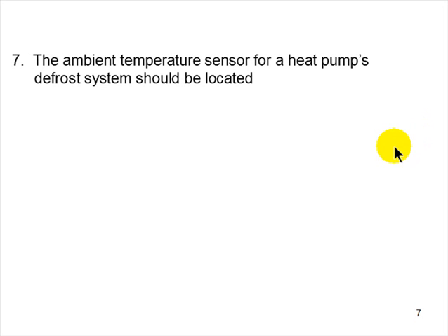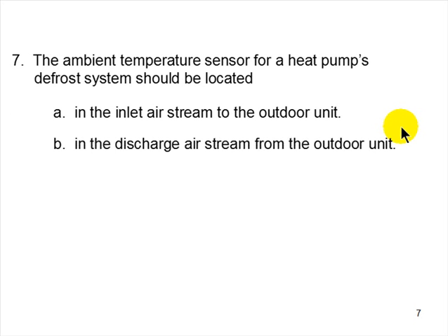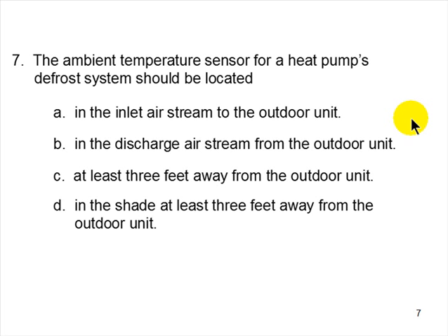Seven, the ambient temperature sensor for a heat pump's defrost system should be located, where do you put the ambient temperature sensor? In the inlet airstream to the outdoor unit? In the discharge airstream from the outdoor unit? At least 3 feet away from the outdoor unit? In the shade at least 3 feet away from the outdoor unit? What do you think? Yeah, in the inlet airstream. If you want to know what the temperature of the air entering the unit is, that's where you put it.